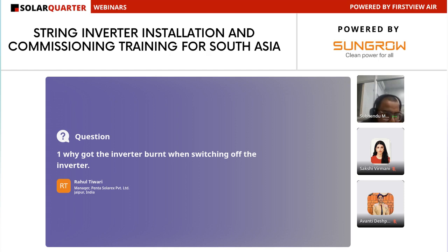Why did the inverter get burned when switching off the inverter? Yes, sometimes what happens is some reverse current occurs from the DC side, and inside the conduit pipe, maybe some rats or insects cut the cable and it short circuits. So it's maybe during the arcing of DC. During the arcing of DC, the inverter will burn.